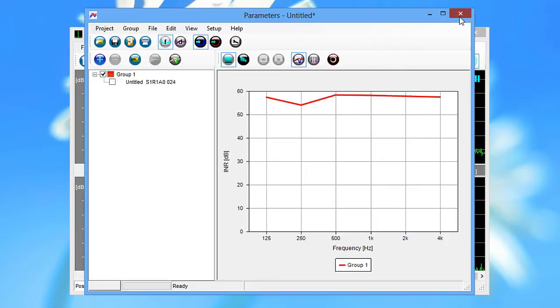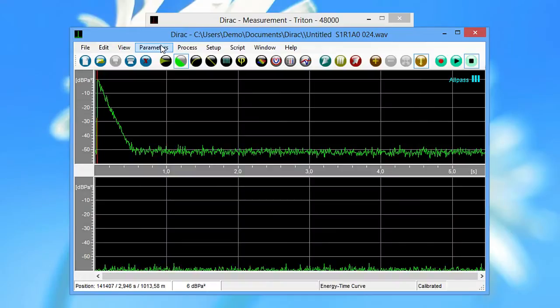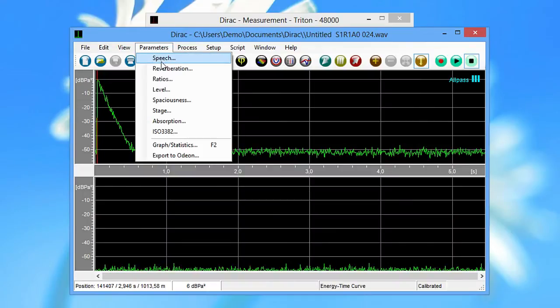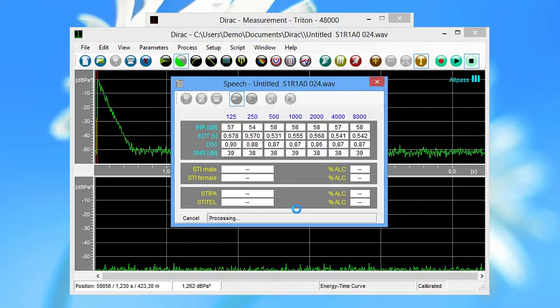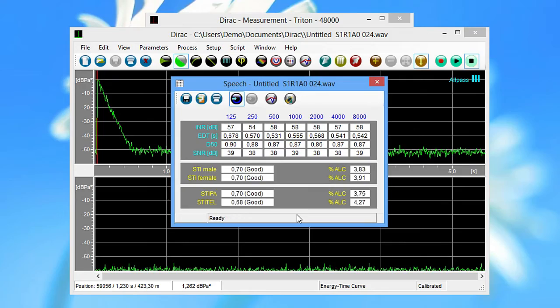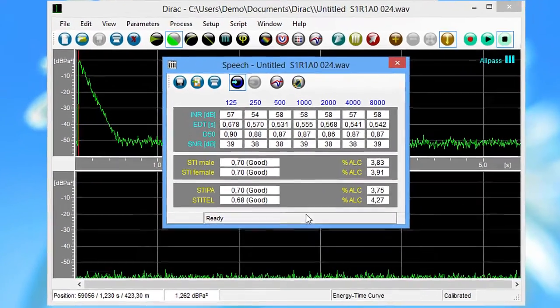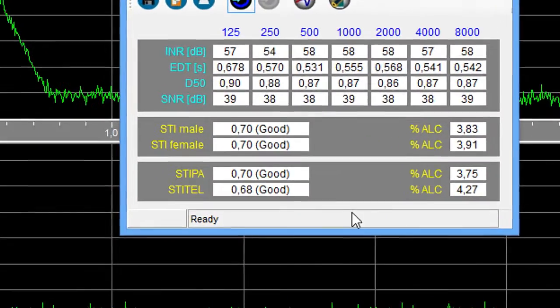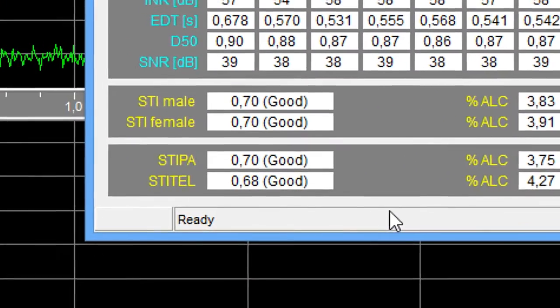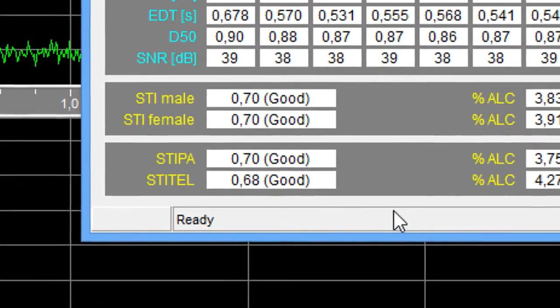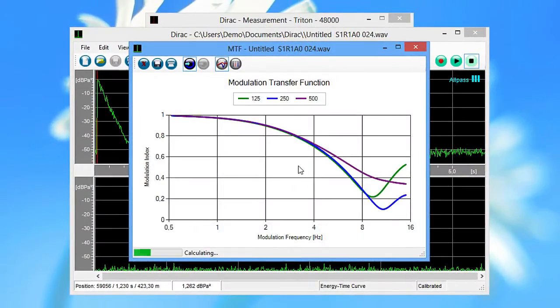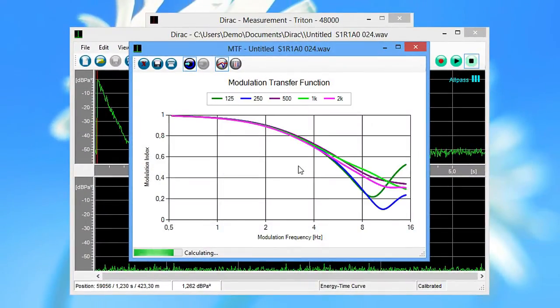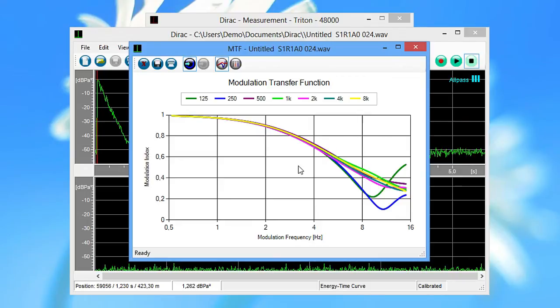With the impulse response looking fine, you can look at the speech intelligibility parameters and see whether the STI is good. If the STI is below expectation, you can use the MTF graph to find whether this was caused by noise or by the acoustics of the room.